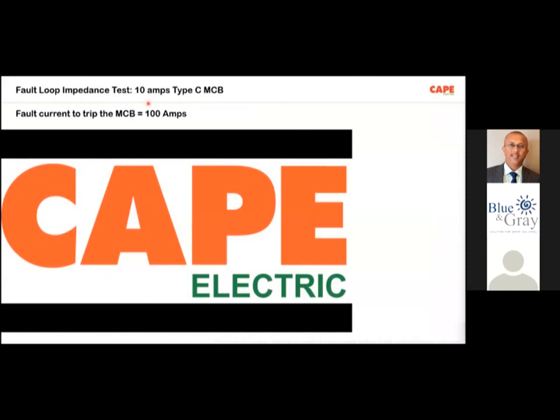For a 10 amps MCB, a circuit where a 10 amps MCB is used. Sometimes people ask, do we need to do the test even for a 10 amps MCB? Yes, of course, you must do the test even for a 6 amps MCB, because most of the time fire starts from small equipment, small connected load. The last fire in Bombay, the newspaper report says, started from a video doorbell. It's a very small item, a video doorbell. Probably it started the fire, but the MCB didn't trip, which has become a major fire accident.